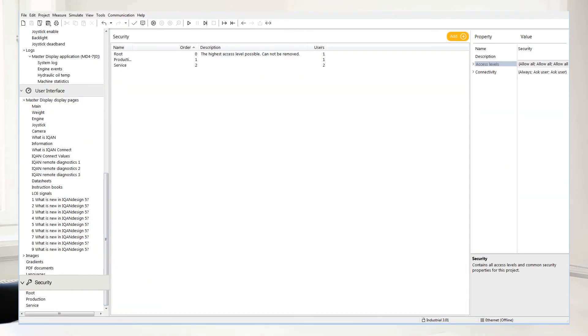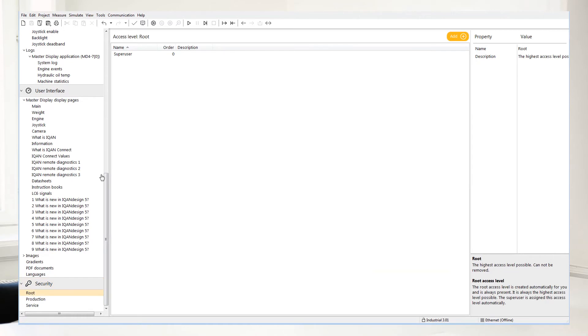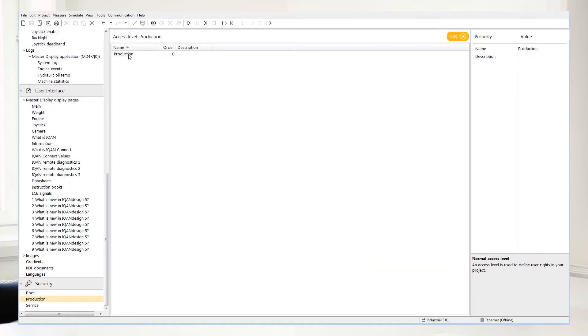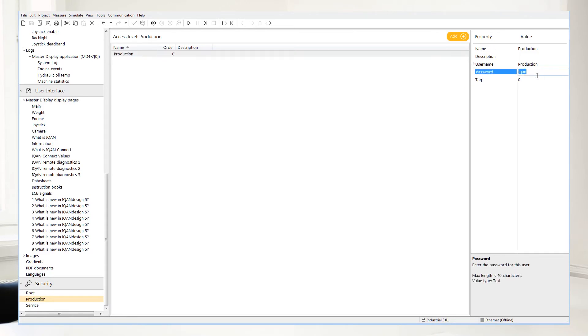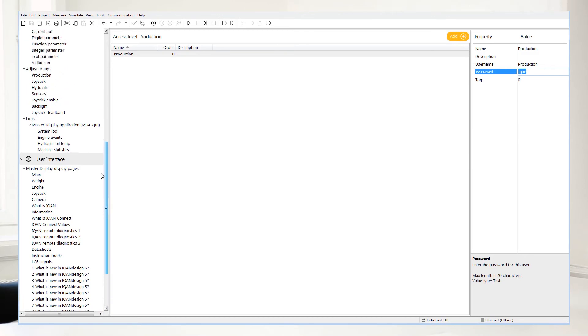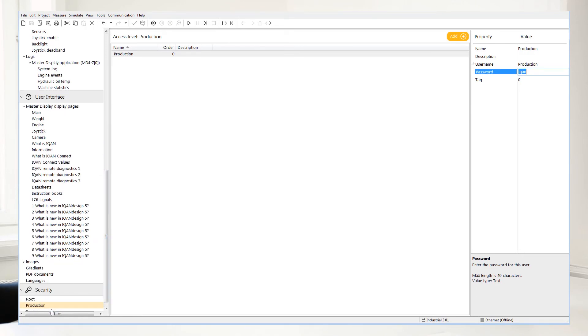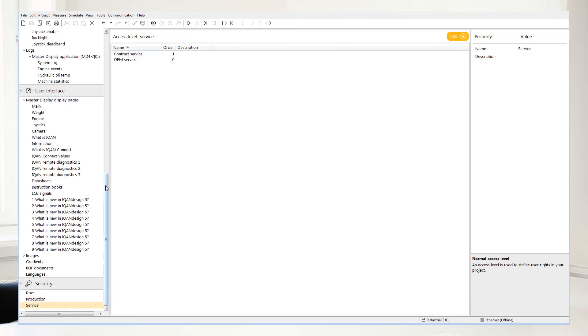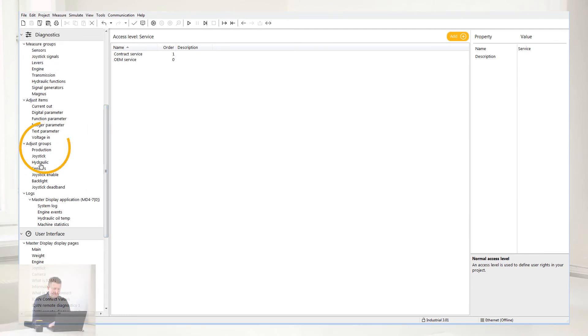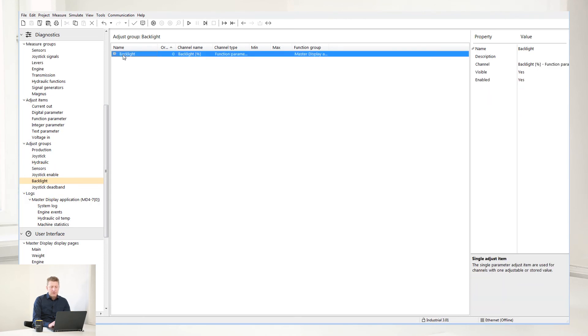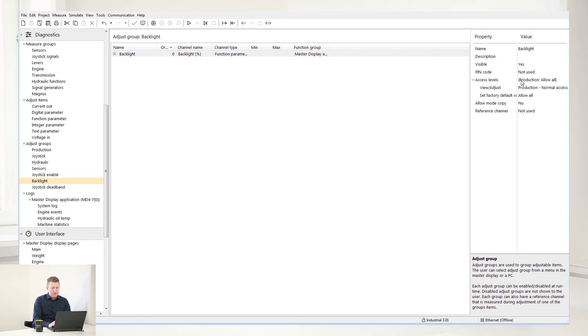And finally, here are the security settings. This is where you can control the different access levels of your machine. If you select production, you can define passwords for your production, so you can log in with a service tool and work on parameter settings that are only open to those with a password. If you select service, you can add different kinds of security levels for service — these are connected to the diagnostic group with adjust items and adjust groups. If you select backlight for example, you can see that the access level for this is production, so only those with production access can access the backlight.